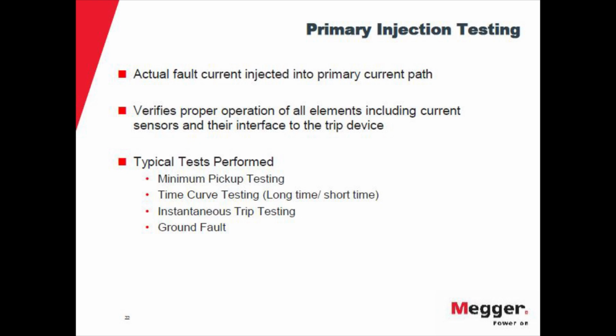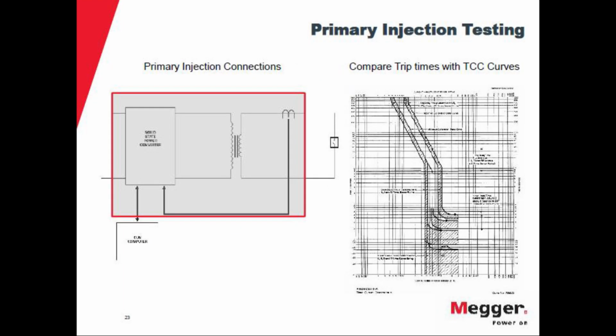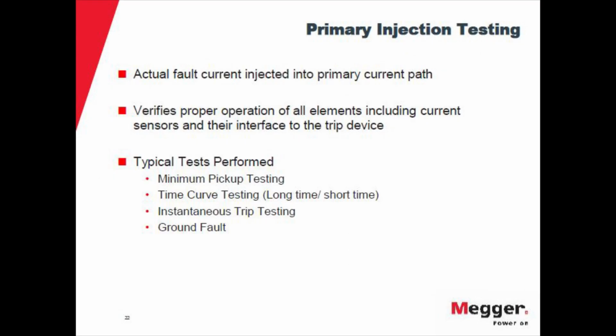Depending on the configuration of the breaker or the elements inside the breaker, you can do minimum pickup testing, time curve testing, instantaneous trip testing, and ground fault testing. So this is the characteristic curve of X, Y, and Z breaker, and this is what it is talking about.